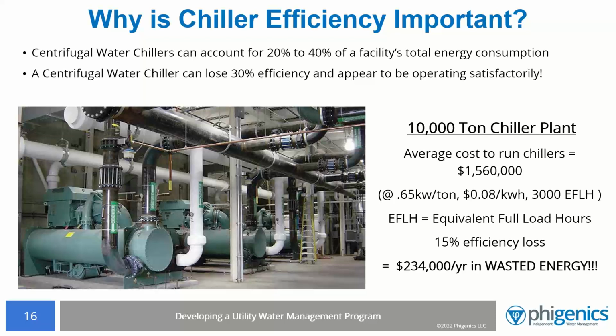This is an example of a typical chiller plant in a large building or small campus complex. The assumptions are that the plant is running at an efficiency of 0.65 kilowatts per ton, that the cost of electricity is 8 cents per kilowatt - if you're still getting that nowadays, it's a lot higher in other parts of the country - and that the equivalent full load cooling hours is 3,000. EFLH is the number of hours a chiller system would have to operate at full load to equal the amount of cooling delivered by the system at a constant temperature over an entire cooling season. So it's essentially how long you're running at full load in the course of a year. And as you can see, with those simple numbers and a 15% efficiency applied, $234,000 is a lot of money in anyone's budget.